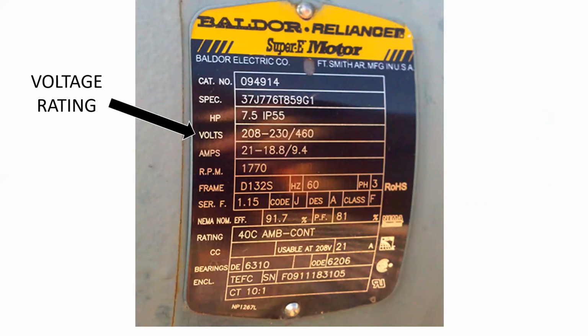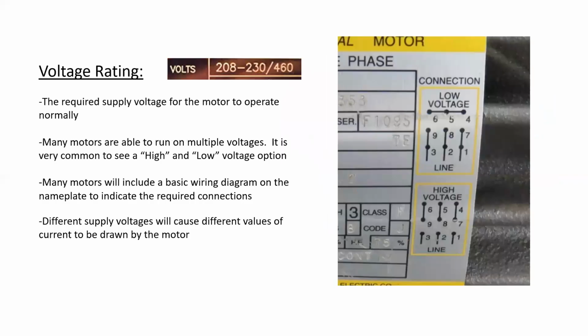Voltage rating. On this motor, we have a voltage rating of 208 to 230 volts / 460. The voltage rating is the required supply voltage for the motor to operate normally. Many motors are able to run on multiple voltages. It's very common to see a high and low voltage option. Many motors will also include a basic wiring diagram on the nameplate to indicate the required connections. And different supply voltages will cause different values of current to be drawn by the motor. This particular motor with the 208-230 means it can operate in the low voltage connection on voltages anywhere from 208 to 230 volts without having any difference of connection. 460 is the high voltage rating, and this would require a high voltage connection inside the motor terminal box with the T leads.